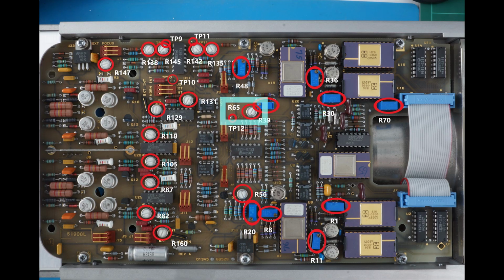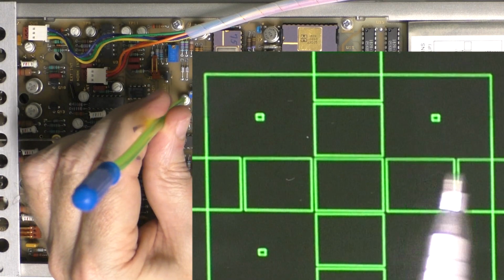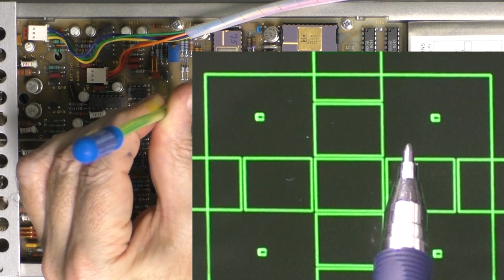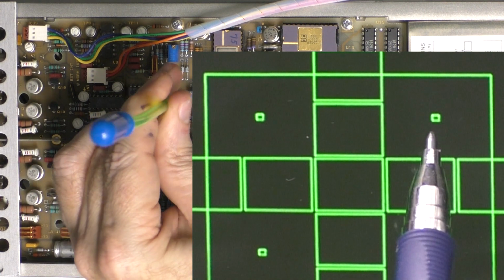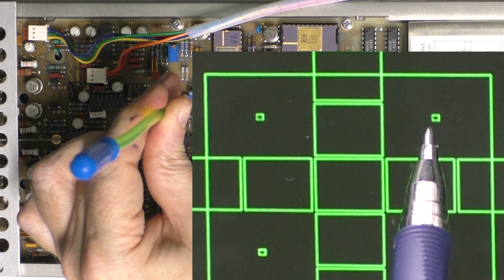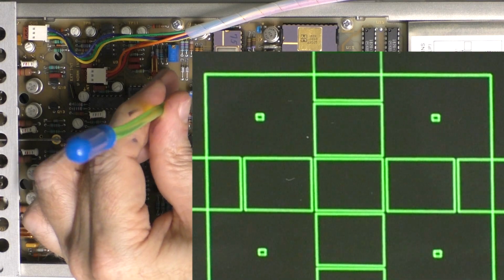Locate R65 on the A1 board. This adjusts the vertical lines ensuring equal intensity. Adjust R65 so that the intensity of the vertical lines of the small boxes are equal. That completes the stroke generator intensity adjustments. We will move on to section 5-16, focus adjustment and resolution check.